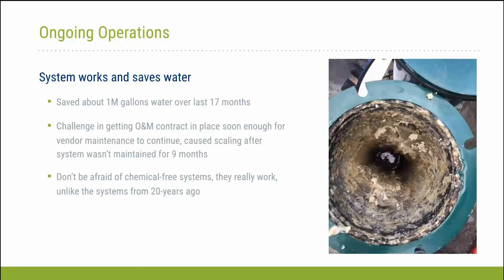Now, some of the maintenance issues we had really arose from our slowness in getting the O&M contract modified to perform maintenance on the unit. And we did have a 9-month period where the unit was not cleaned at all. What happened was we had some slime buildup and a little bit of scale buildup on one of the oil coolers, or oil pumps, for the chiller. Once we got the O&M contract in place and we're performing the regular cleanings, even without any changes to the settings, the unit was working just fine again, and we weren't having any buildup anywhere in the system, and the cooling towers were still looking pretty clean.